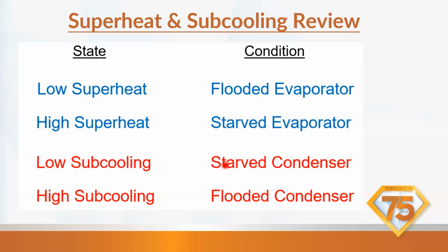Low subcooling is a starved condenser. So now we're moving to the outdoor unit. We could be starving the condenser, not enough refrigerant. We've got to add refrigerant if we have a low subcooling. If we have a high subcooling, say we have a 20-degree subcool in cooling, we have a flooded condenser.